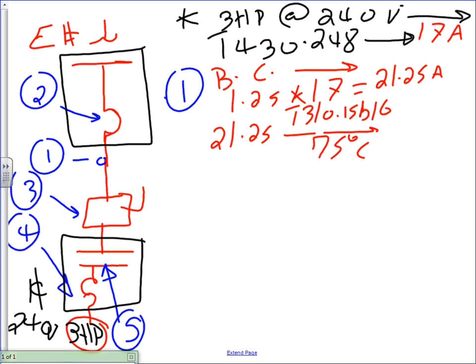I have 21 point, so my next standard is number 12, right? How many conductors? It's a 240, so 2 conductors, number 12 AWG. Now remember, number 12 cannot carry more than 20 amps. Motors are an exception. You remember how we went through that? And what type of insulation am I using? I'm using THHW. So I'm putting in a conduit, pulling THHW inside it, 2 conductors. Any question about this?